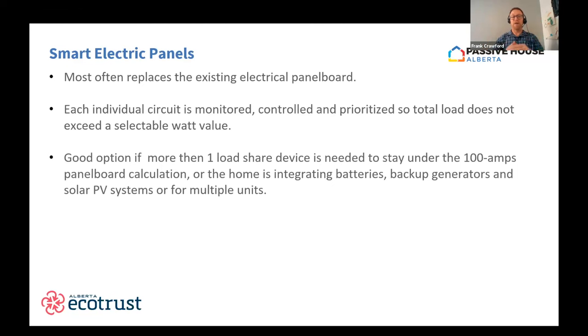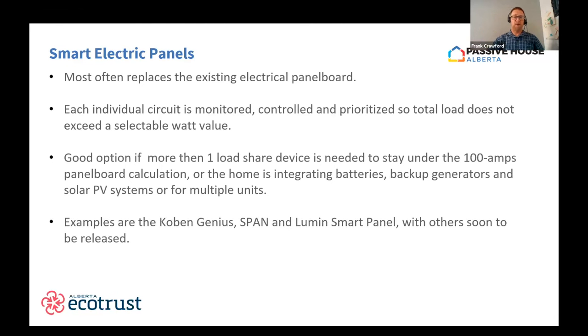So it's a good option if you need more than one load share device to stay under that 100 amps, or if, as part of your retrofit or new build, you're looking to integrate batteries, a backup generator, a solar PV system, or multiple different units in a house, then these smart electrical panels might be a good option. There are a number of them available. The Koben Genius is the most available in Canada. Span isn't currently available in Canada. The Lumin Smart Panel is, and there are a few other ones that are soon to be released. The downside to these is they cost at least about $5,000 to buy, and the labor is much more intensive because you're basically reconnecting all of the individual circuits.